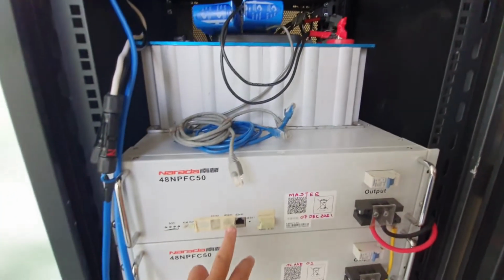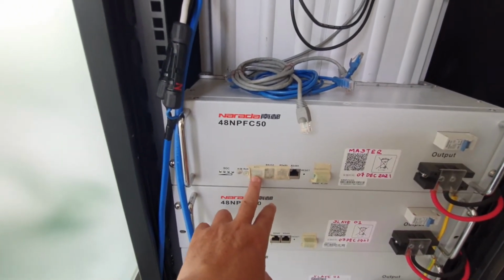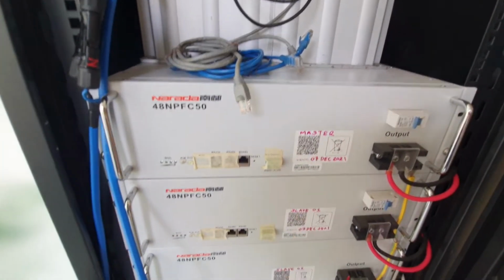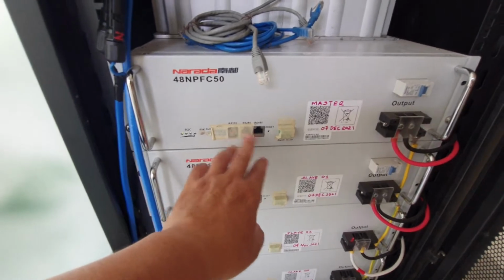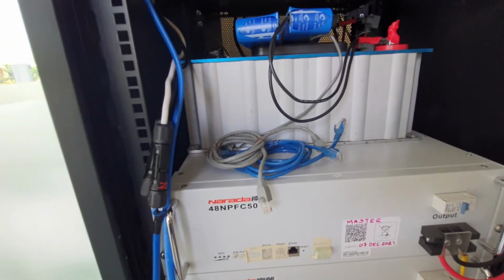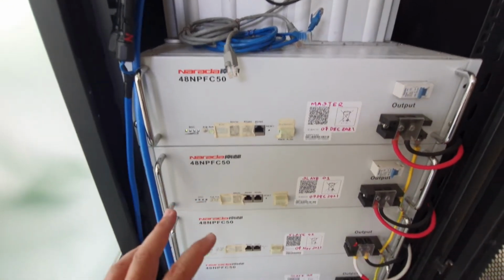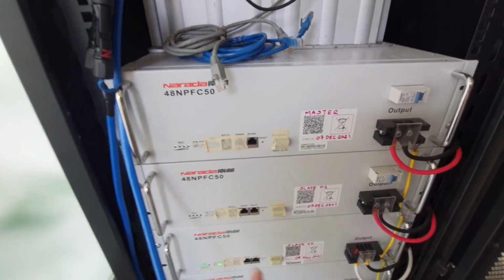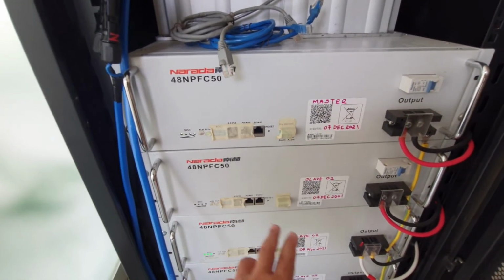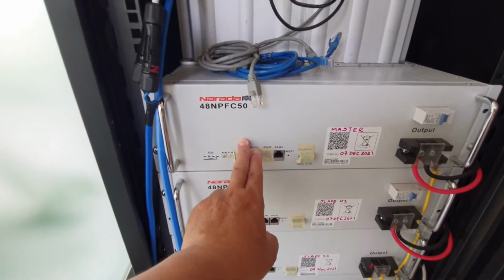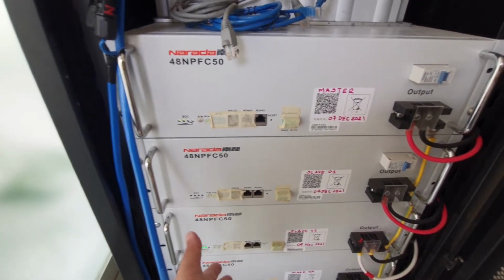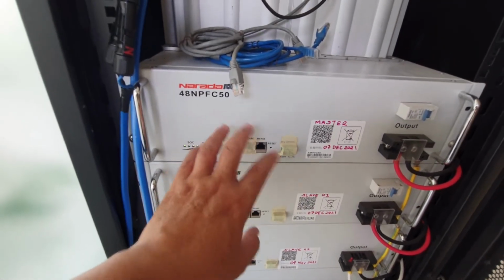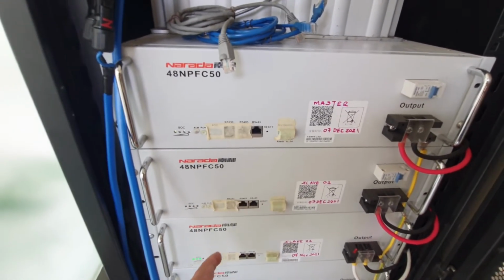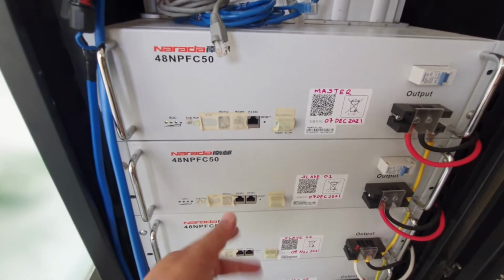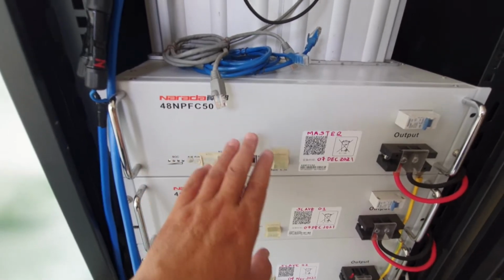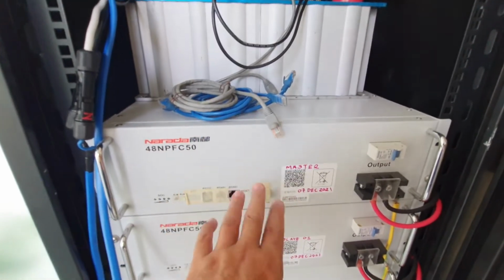They have communication cables, and this is the ID: master, slave 1, 2, 3. But I didn't plug in the communication cables, because I find that when the master controls the others, it charges the master first, then the next one at a lower rate, randomly choosing which charges first each day. The master must be charged up, and the master will be the last to drain. This is programmed inside.